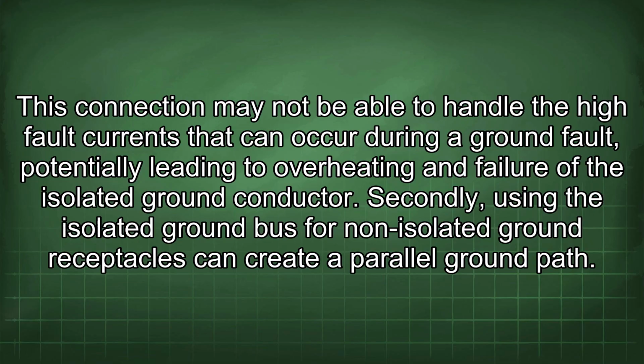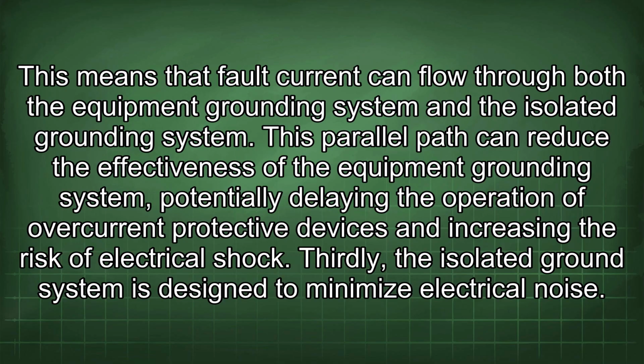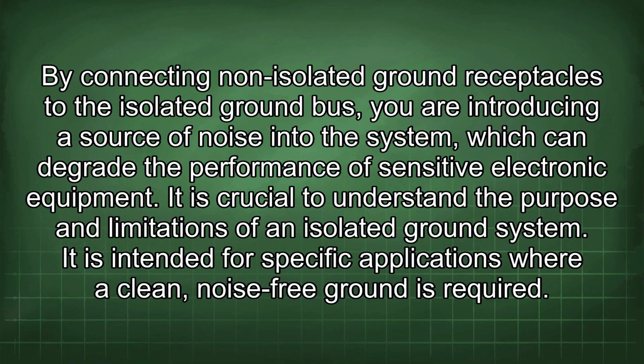Secondly, using the isolated ground bus for non-isolated ground receptacles can create a parallel ground path. This means that fault current can flow through both the equipment grounding system and the isolated grounding system. This parallel path can reduce the effectiveness of the equipment grounding system, potentially delaying the operation of overcurrent protective devices and increasing the risk of electrical shock. Thirdly, the isolated ground system is designed to minimize electrical noise. By connecting non-isolated ground receptacles to the isolated ground bus, you are introducing a source of noise into the system, which can degrade the performance of sensitive electronic equipment.